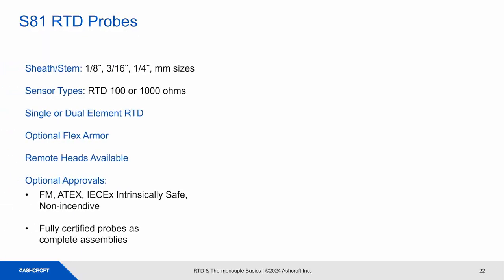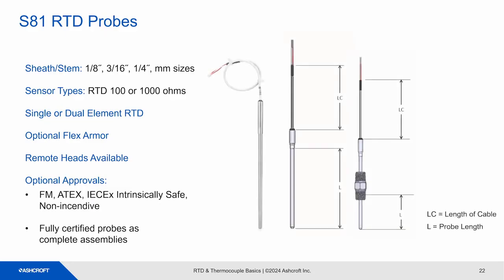S81 remote mount RTD probes. Common sheath diameters are 1/8, 3/16, 1/4, and 6 and 8 millimeter sizes. S81s offer the 100 and 1000 ohm RTDs. They're available with optional flex armor and remote heads. For approvals, we offer FM, ATEX, and IECEx intrinsically safe and non-incendive approvals. The images show how the probe length and cable length are measured. If we install a spring-loaded fitting like the image on the right, the L length is defined from the bottom of the threads to the tip of the probe, the same as on the S80 probe.